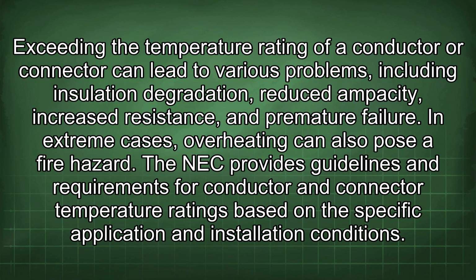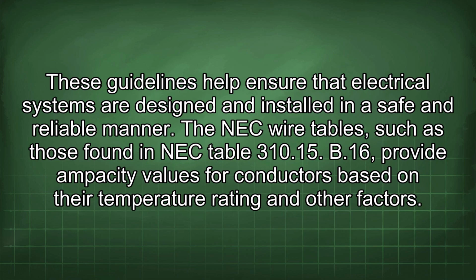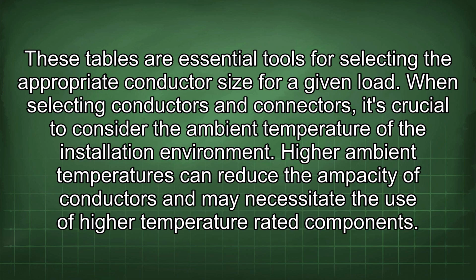The NEC provides guidelines and requirements for conductor and connector temperature ratings based on the specific application and installation conditions. These guidelines help ensure that electrical systems are designed and installed in a safe and reliable manner. The NEC wire tables, such as those found in NEC Table 310.15(B)(16), provide ampacity values for conductors based on their temperature rating and other factors. These tables are essential tools for selecting the appropriate conductor size for a given load.